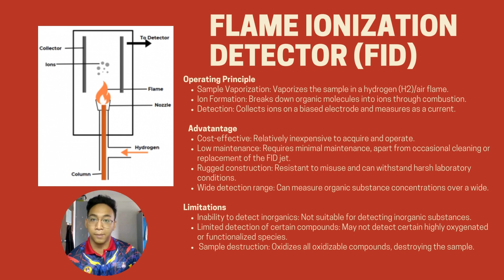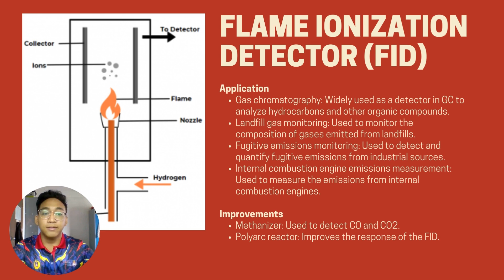oxidizable compounds. The flame ionization detector is the most widely used detector in gas chromatography due to its reliability, versatility, and ease of use. It operates by detecting the ions produced when organic molecules burn in a hydrogen flame, which are proportional to the amount of carbon in the sample. The FID is sensitive to most carbon-containing compounds, with a linear range of 7 orders of magnitude and a detection limit in the picogram range. It is commonly used in environmental analysis, the petrochemical industry, and internal combustion engine emission measurement, and is particularly effective for detecting hydrocarbons and other organic compounds.